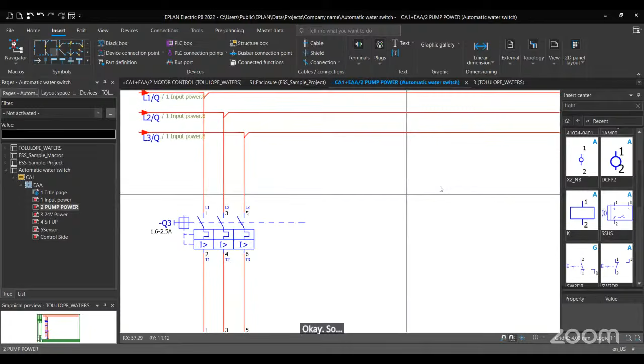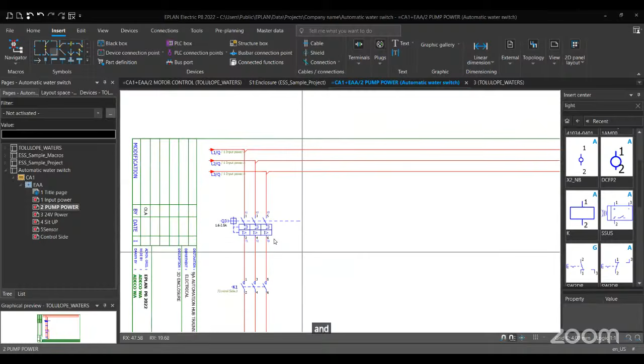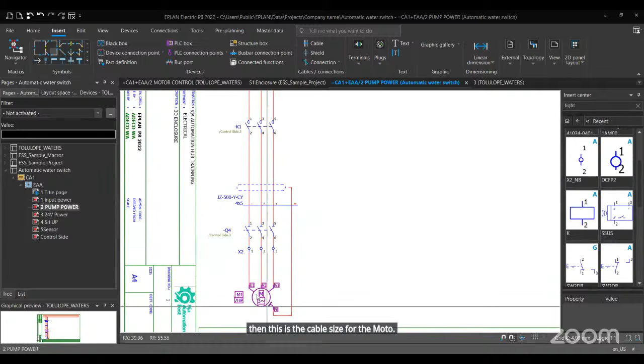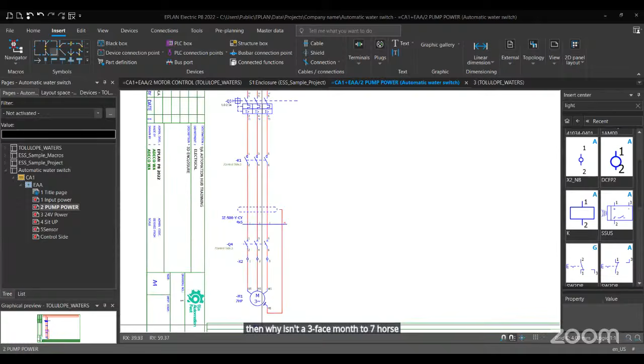Okay. So, like I said, some people make use of overload relay and breakers, which is super okay also, no discrimination. Then we have contactor, the K1 we're using for the motor, we're using DOL control, not too much drama. Then your motor also has an isolator, the one connected on field close to the motor, in case you want to work on the motor instead of going to your panel to switch it off and all of that. Then this is the cable size for the motor. This is the earthing route for the motor. Then we're using a three-phase motor, 7 horsepower, like I stated, DOL, M1, the label for the motor.